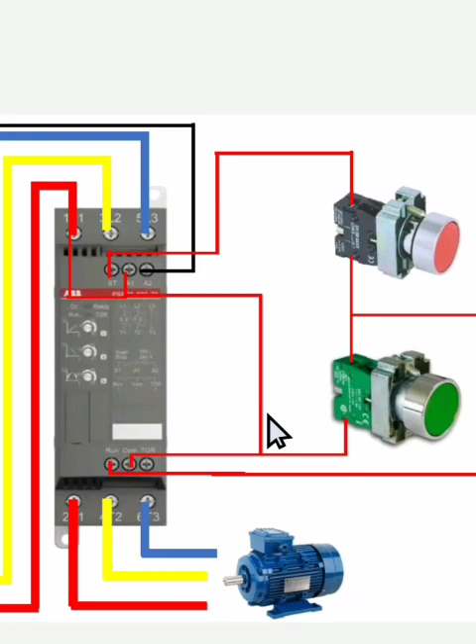Let me show you something. If you look closely here, we can adjust the ramp starting and stop time, like a star-delta start which proceeds from star to delta. But here we can control the inrush current with these three potentiometers, causing it to start with any particular voltage or current. It starts very slowly, so there's barely any draw on the supply. That's the beauty of the ABB soft starter.